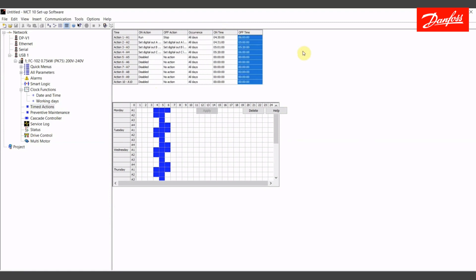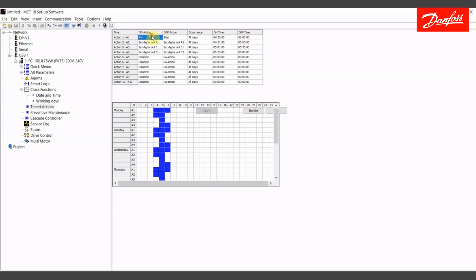Let's start out with our first action, which is going to be to start and stop this drive between the hours of 4:30 and 6 a.m. We're going to assume that the basic drive programming has already been done. It has been configured with proper motor data, possibly in a closed loop configuration with the set point entered, a pipe fill mode at first startup in the morning. This is just going to tell the drive when to turn on and off and control the zones.